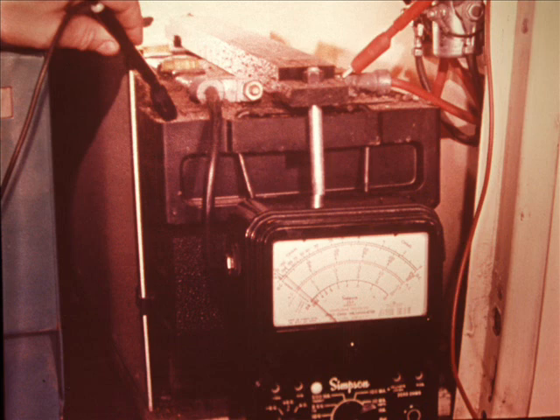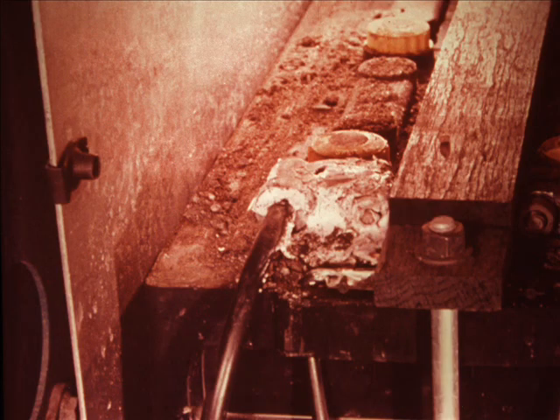Especially expect it to discharge if the top is dirty, since this creates a high resistance path for electrical flow between the terminals. You can prove this by measuring a definite voltage between the positive terminal and the top of a dirty case. Third, expect it to not function properly and even to fail early if not properly maintained.